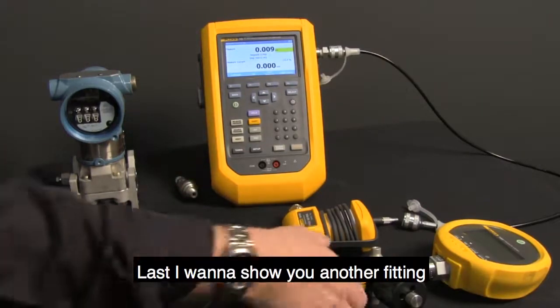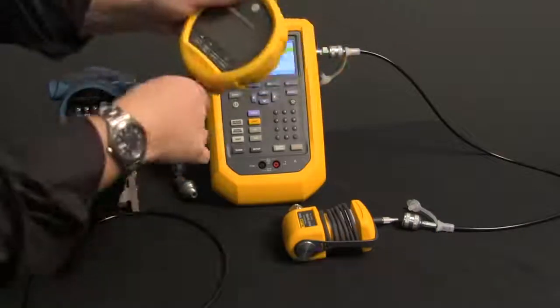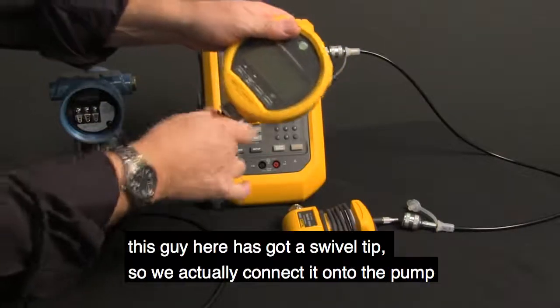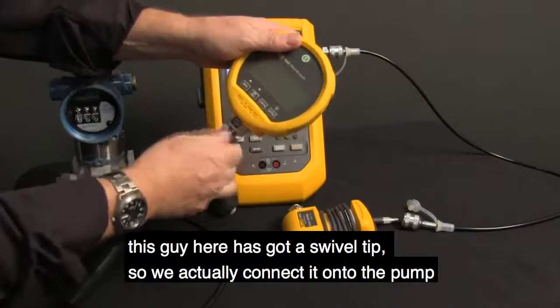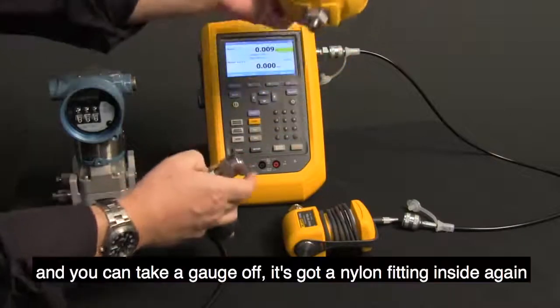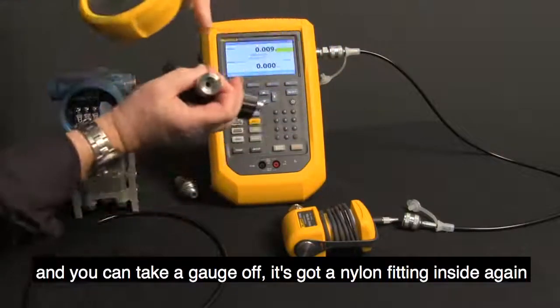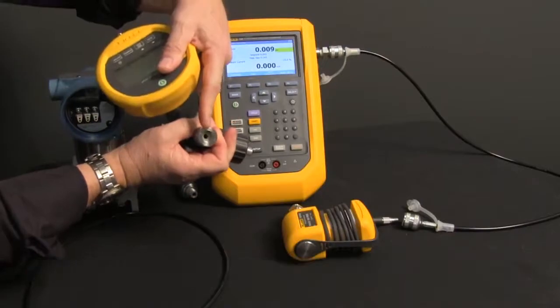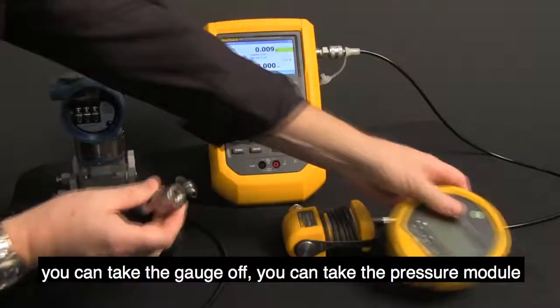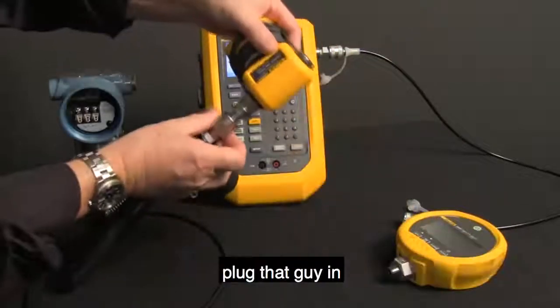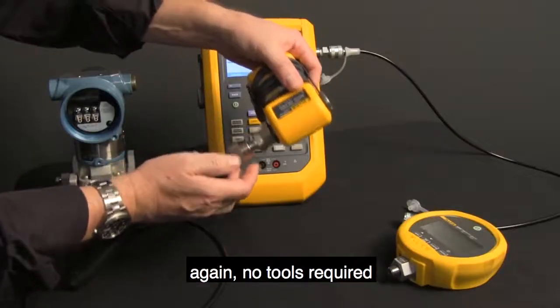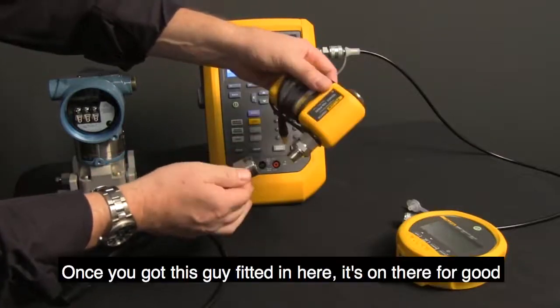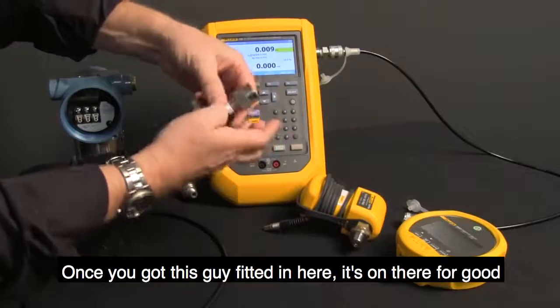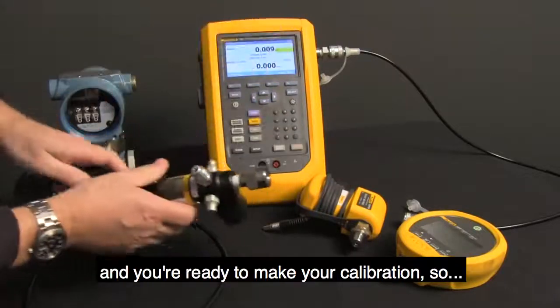Lastly, I want to show you another fitting. This guy here has got a swivel tip, so we actually connect it onto the pump, and you can take a gauge off. It's got a nylon fitting inside again. You can take the gauge off. You can take a pressure module, plug that guy in. Again, no tools required. Once you got this guy fitted in here, it's on there for good, and you're ready to make your calibration.